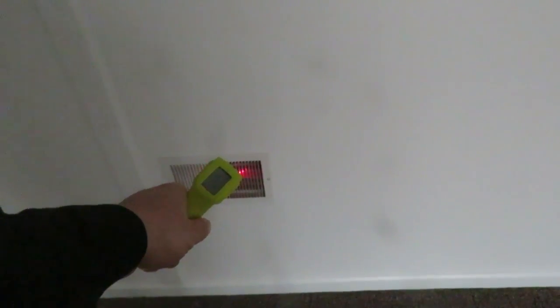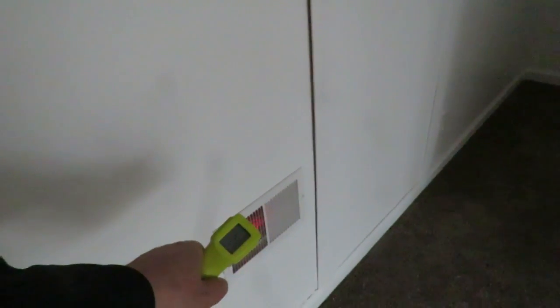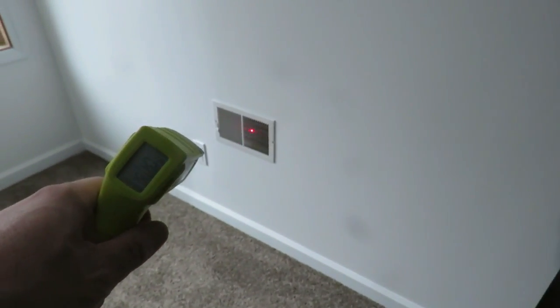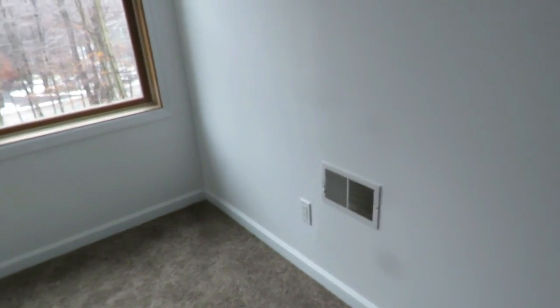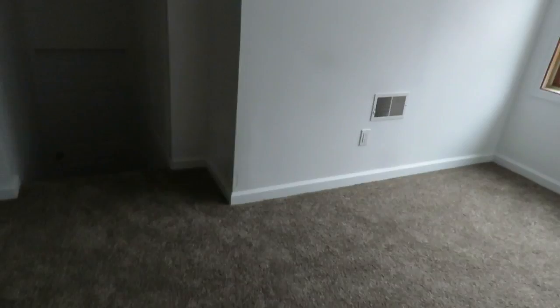Okay, here we are up in the loft area that's been finished. There's some attic access right behind these access doors here. What we found up here is when we test these registers with our heat gun, we're getting 118 degrees blowing out of this register, but we're not getting any heat blowing out of this register or either of these two. So that would be an indication that the ductwork may not be hooked up. The rest of the system is blowing fine, but those three have no heat coming out of them. So we of course are going to put that into our report and into our findings.